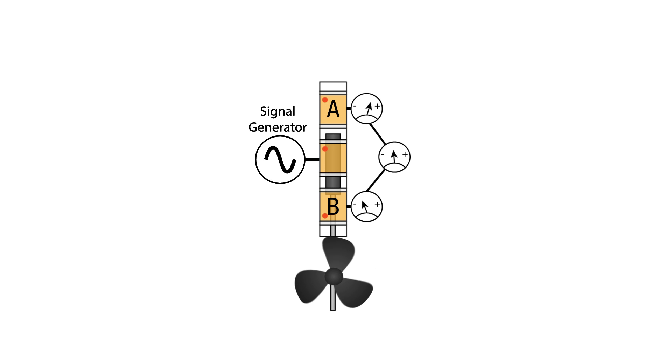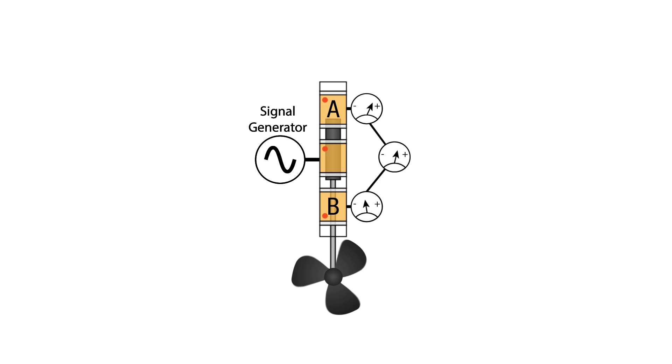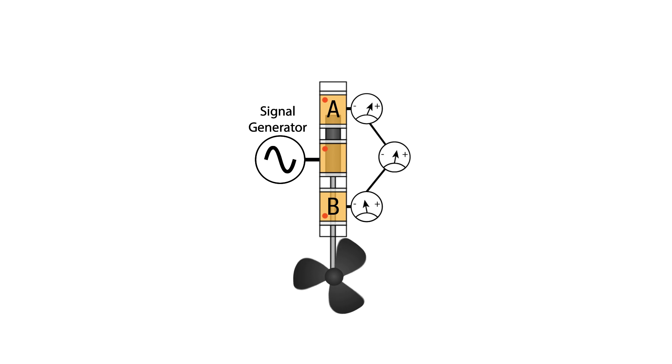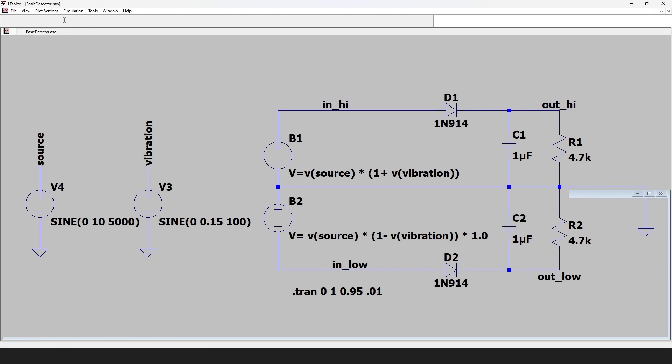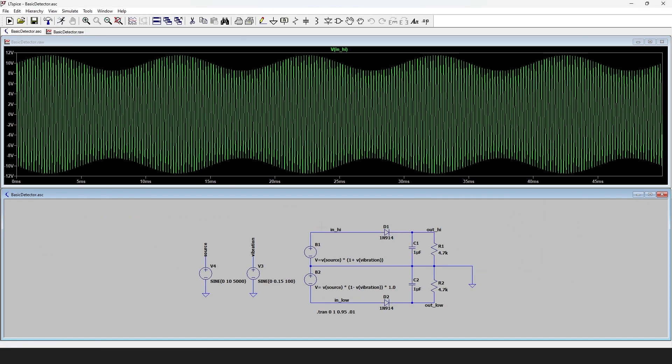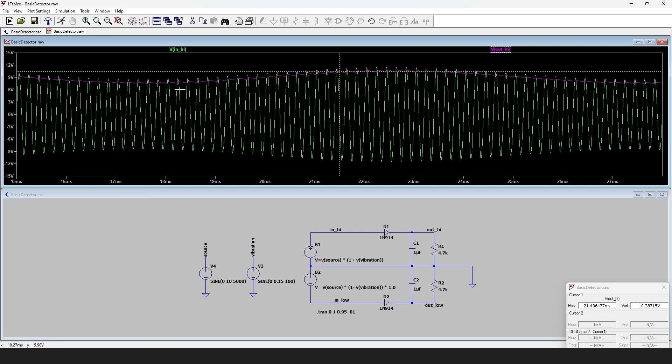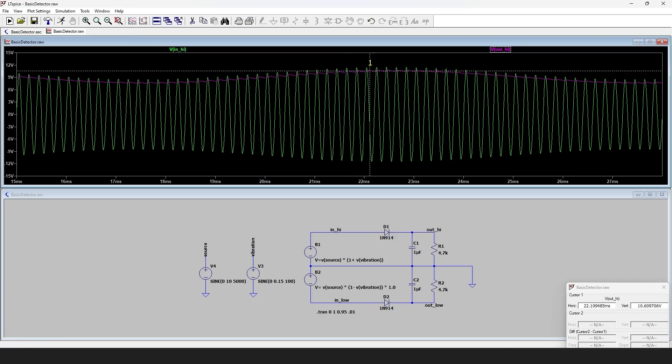So this explanation is a little misleading. If we measure an AC voltage with the analog meter it will simply show the amplitude and not give a care about the phase. So we need a detector circuit that will rectify and fill in the gaps of the sine wave so that we're left with a DC voltage indicating where the rod is within the stroke of the LVDT.